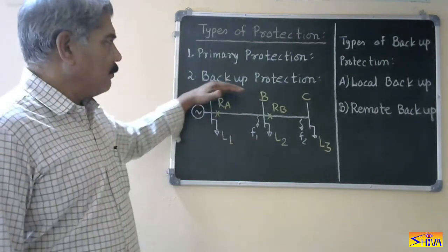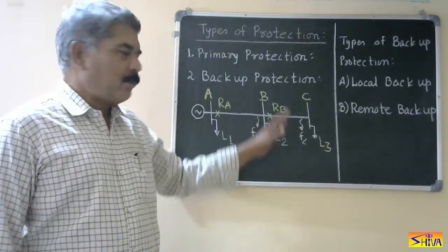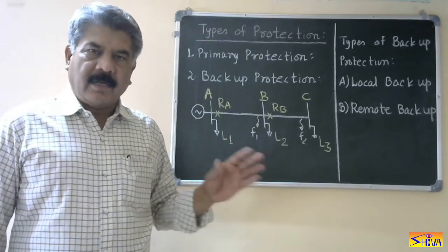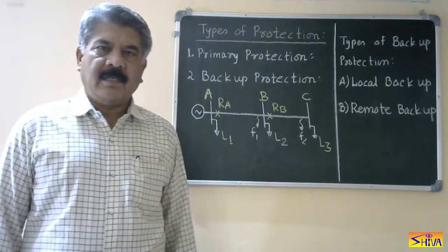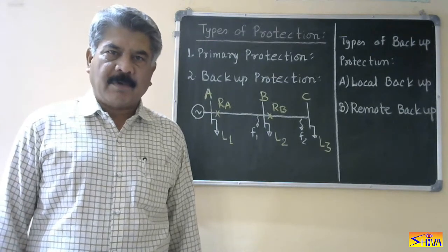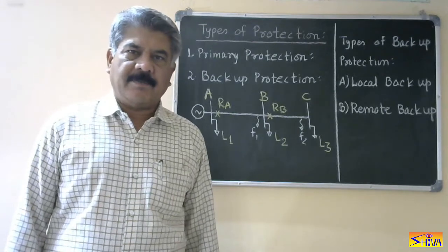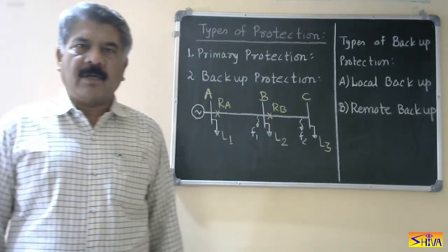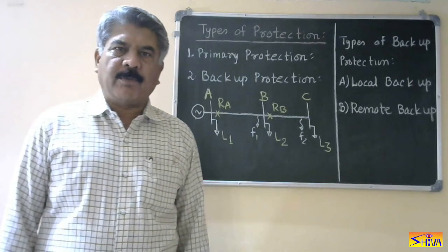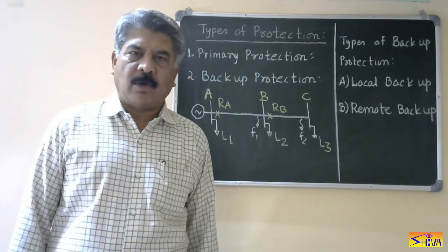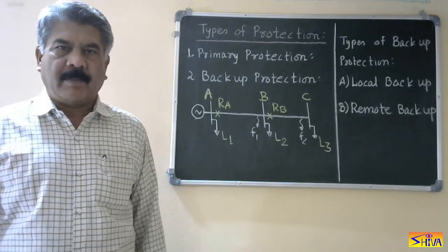Now let us see what is backup protection. When we consider the entire protection system, it consists of a relay, circuit breaker, CT, PT, trip coil, DC power supply, and the complete trip circuit. There is a probability of failure of any component, and when any component fails, the entire protection system fails to operate. So we cannot eliminate the possibility of failure of primary protection.